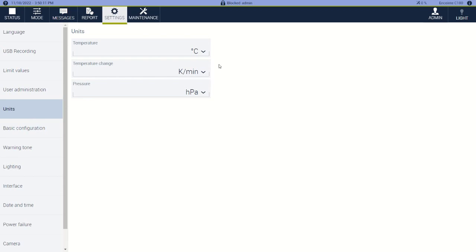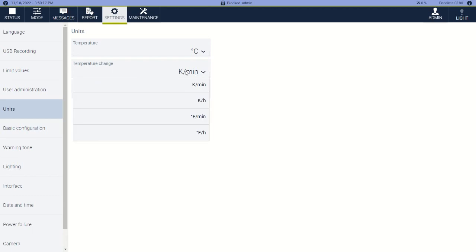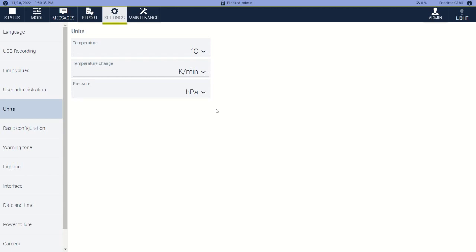We also have different units. Here we've been using Celsius, but you can also use Fahrenheit or Kelvin. We have Kelvin per minute, Kelvin per hour, Fahrenheit per minute, Fahrenheit per hour. Kelvin per minute is the same as Celsius per minute. And then if your chamber is using pressure readings, we can do Torr, psi, or pascals.